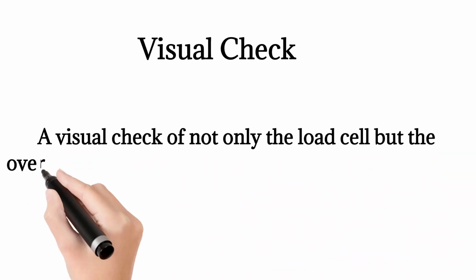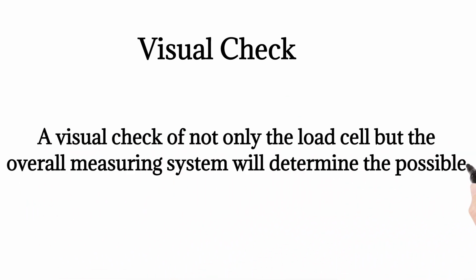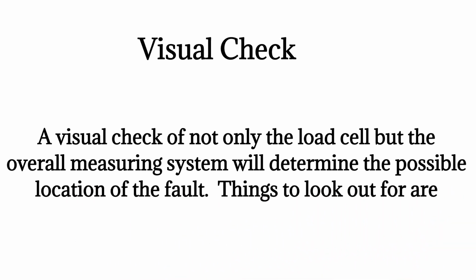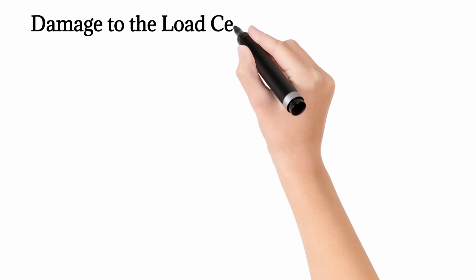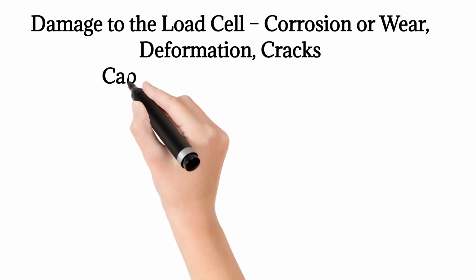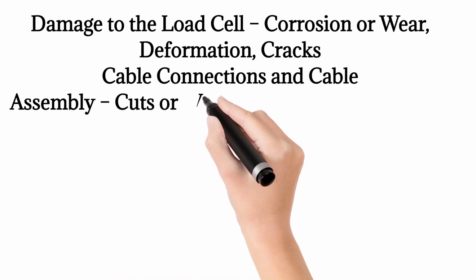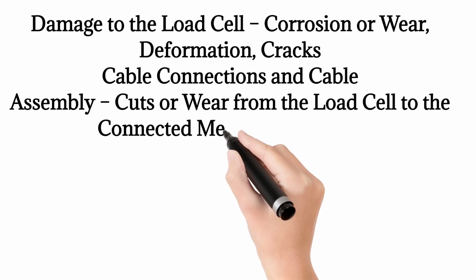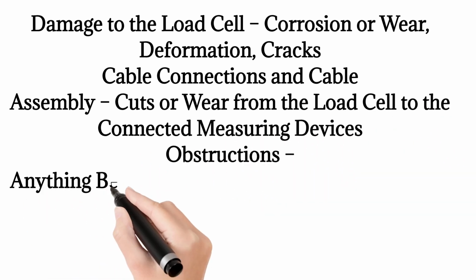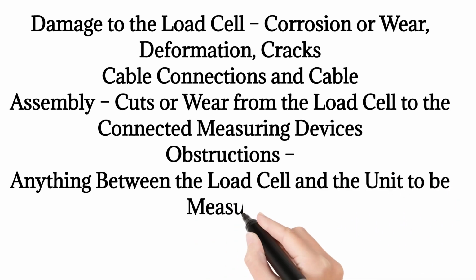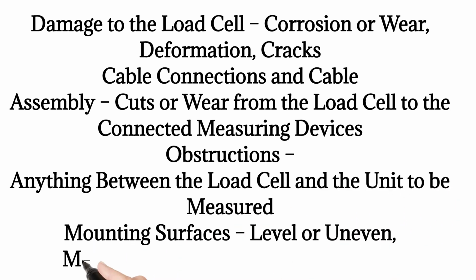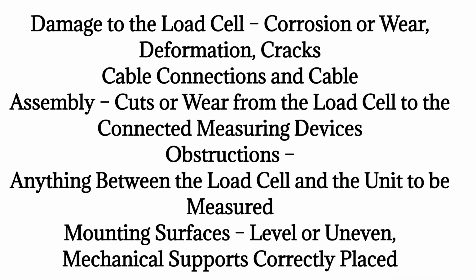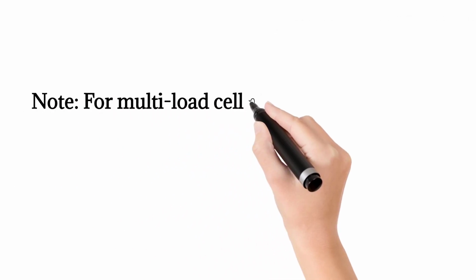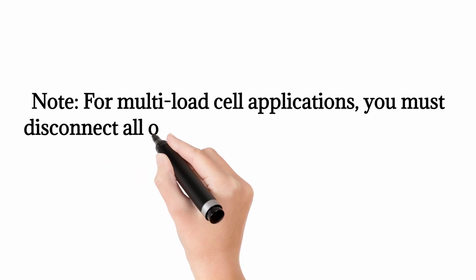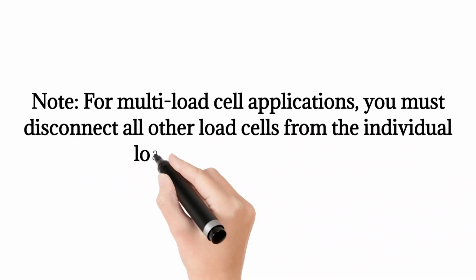Visual check. A visual check of not only the load cell but the overall measuring system will determine the possible location of the fault. Things to look out for are damage to the load cell, corrosion or wear, deformation, cracks, cable connections and cable assembly, cuts or wear from the load cell to the connected measuring devices, obstructions, anything between the load cell and the unit to be measured, mounting surfaces, level or uneven, mechanical supports correctly placed. Note: for multi-load cell applications, you must disconnect all other load cells from the individual load cell you are testing.